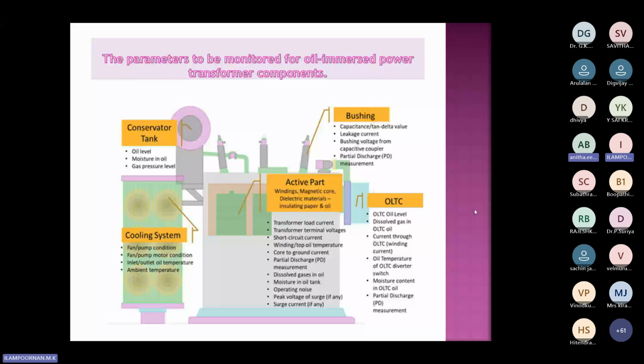Yes, sir. Okay. So if the oil expands, there will be some air in the conservator tank. Where will that go? It will go through the vent gap to the breather. Is there anything in the breather? Yes. We call it a silica gel breather. Why are we keeping the silica gel there? To absorb the moisture content.